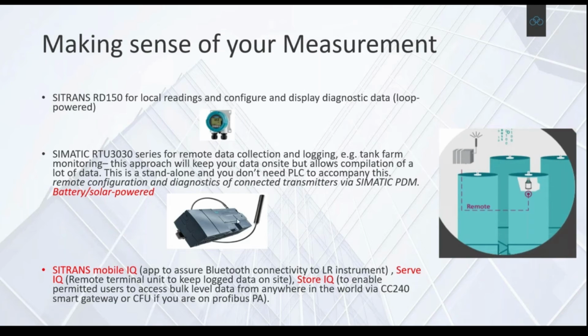The RTU comes into its own when you're off-site, for example if you only want warnings when the level reaches below 30%. It will export those warnings every 5, 10, or 15 minutes, every hour, for as long as the level remains below 30%.